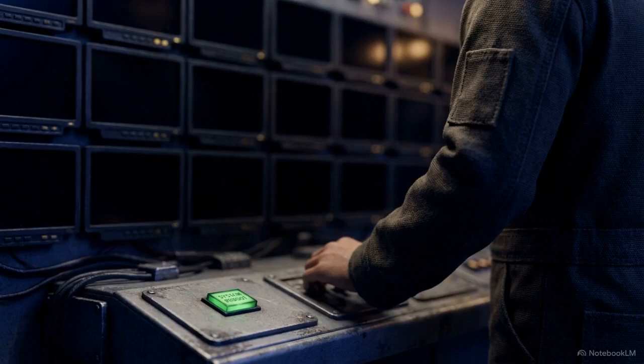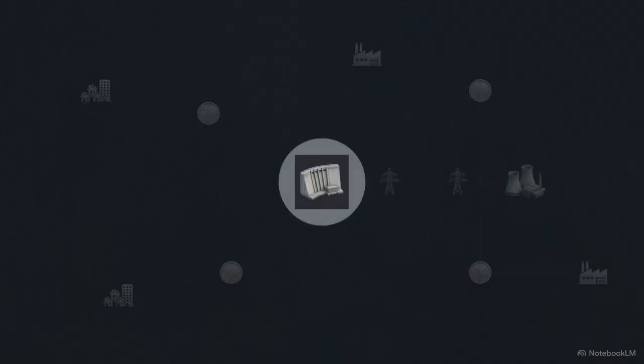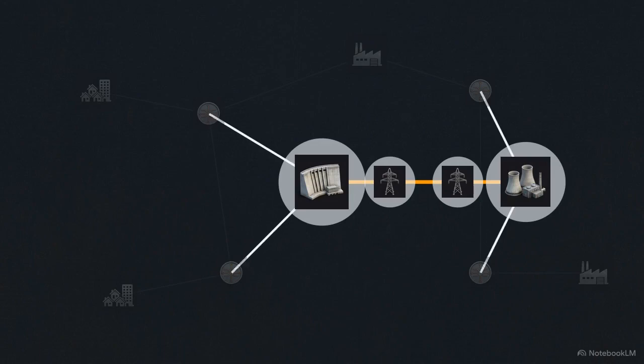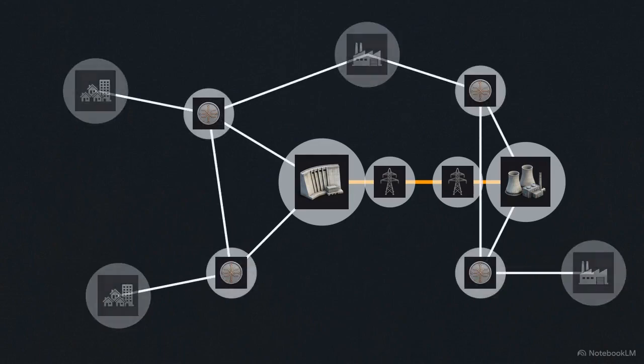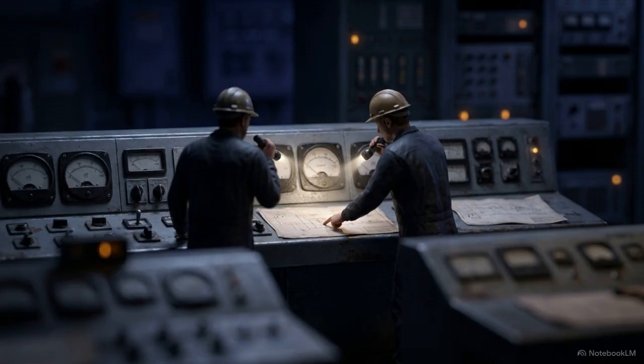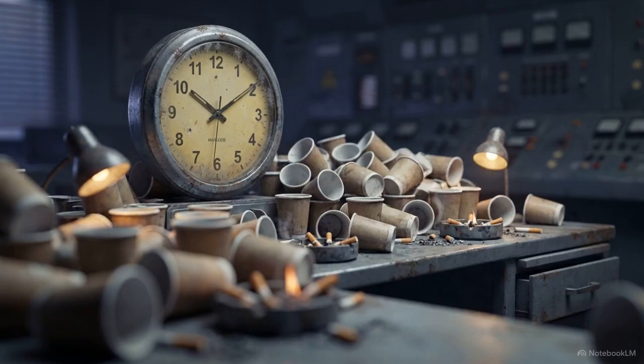Restoring the system is an intensive engineering challenge. Operators must perform a black start, jump-starting the grid from zero without any external power, and carefully resynchronizing every plant and substation across the country. In Pakistan's 2021 blackout, the lack of modern visibility and black start facilities reduced top engineers to blind trial and error. It took 20 hours to restore power to the nation.